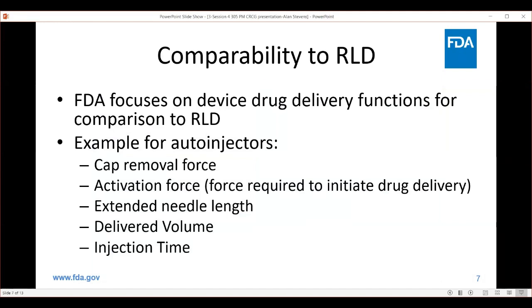Okay, so when we look at the device, there's a couple of things we're looking at from a performance standpoint. One is the comparability of the device to the reference product in terms of its performance specifications. And then we're looking at the actual performance data as well. When we talk about performance characteristics in CDRH, what we're primarily concerned about for comparability are those that impact the drug delivery function. So for example, for an auto-injector, the extended needle length, the injection time, the activation force; cap removal force could also be a key consideration depending on the product. These are the attributes where we look at how your product compares in terms of its specification range to the reference product.